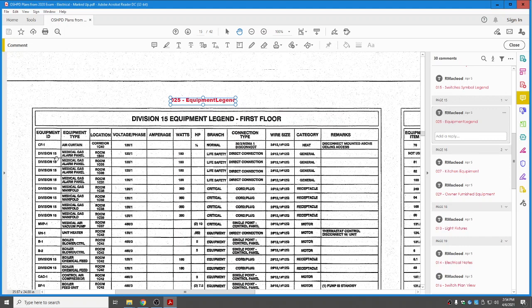If you look at the headers along the top, you'll see equipment ID, equipment type, location, in other words what room, voltage and phase, watts, horsepower, what branch of the system, is it normal or E-power, and on E-power, is it life safety, critical, or equipment branch, the connection type, cord and plug, or hardwired in, to a disconnect or a J-box, what is the wire size that will be used to connect that piece of equipment up, category, and remarks. All right, so let's go ahead and take a look at CF1, an air curtain, which is in corridor 1C40.